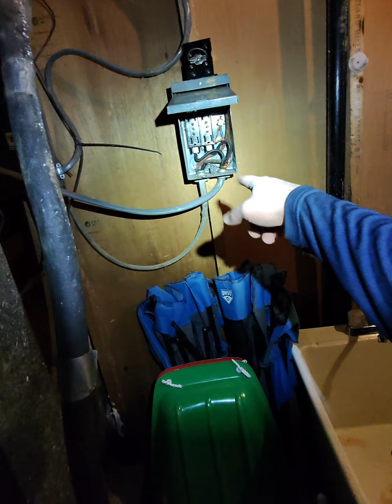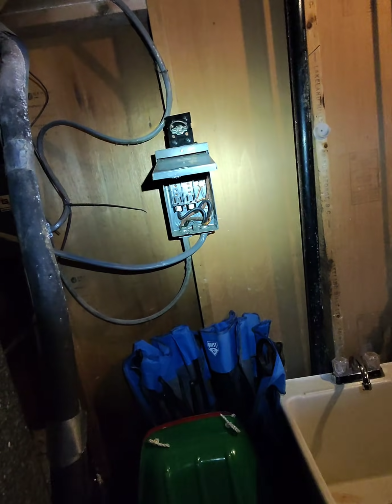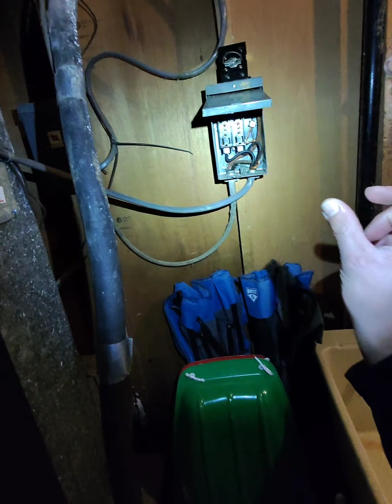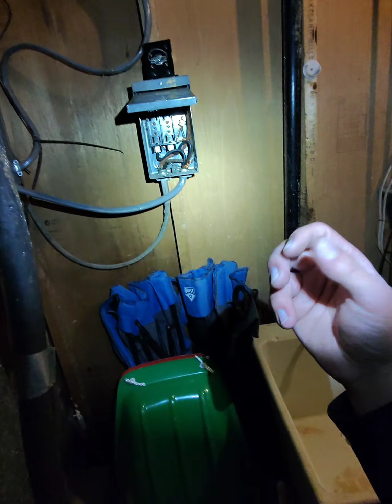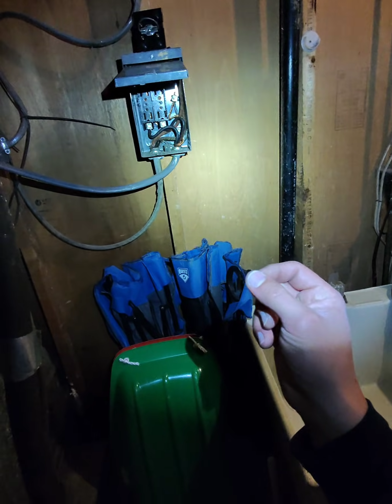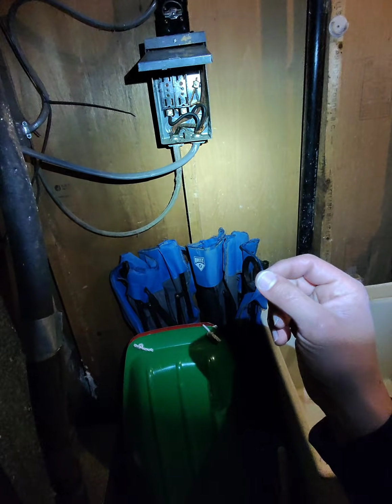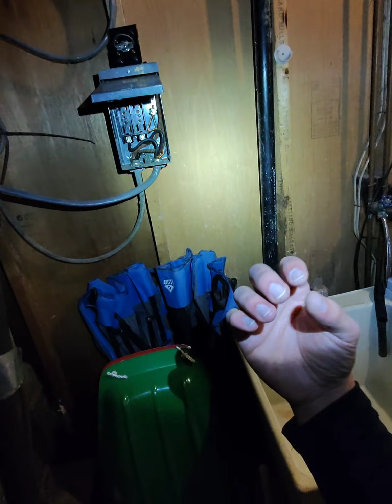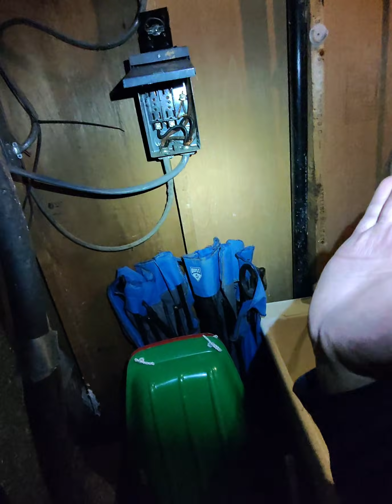At the same time, once we restore that, I'll have Nelson check the circuit panel to make sure the circuit breaker itself doesn't have an issue. Sometimes circuit breakers build resistance, and if that resistance builds up sufficiently, it starts to overheat. When it overheats, it then opens and triggers.